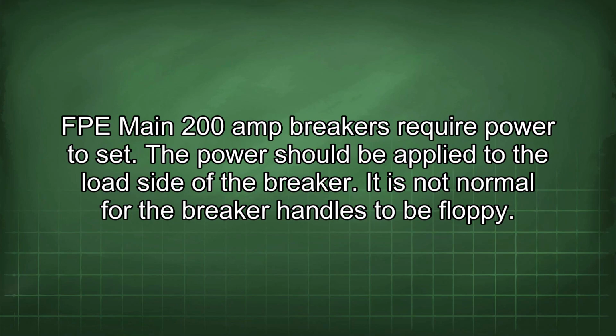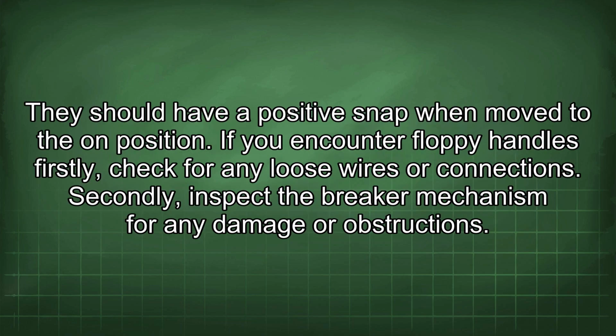FPE main 200 amp breakers require power to set. The power should be applied to the load side of the breaker. It is not normal for the breaker handles to be floppy. They should have a positive snap when moved to the on position.